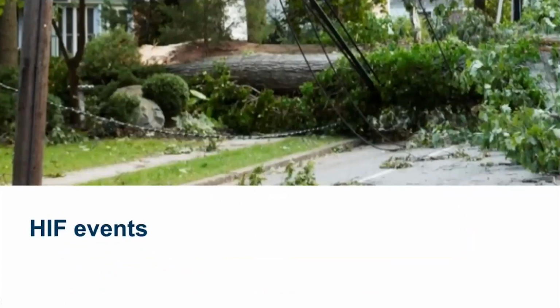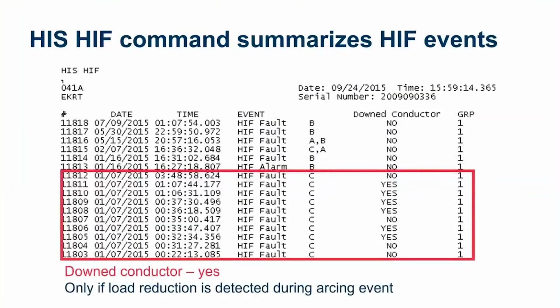Thank you. I'm going to continue the presentation of the discussion on high impedance faults. So Anthony talked about how the ArcSense technology works and how it detects a high impedance fault or a down conductor. And then we talked about the settings. Next, I'm going to talk about the high impedance fault events. Like what do the events look like? What information do you get from the events and things like that. And I'm going to talk about one event from an actual field event that we're going to talk about in a little more detail.